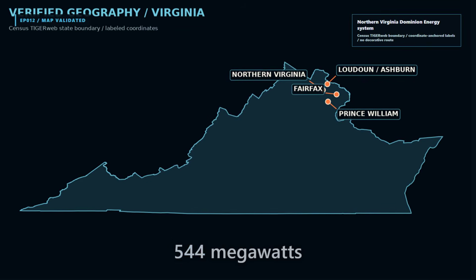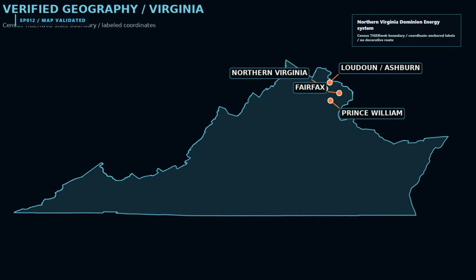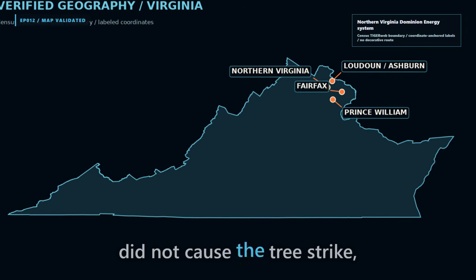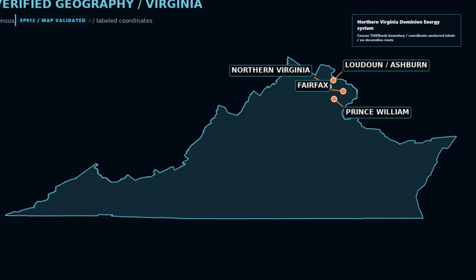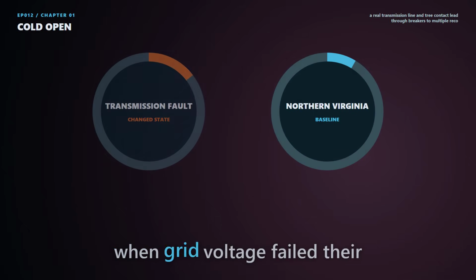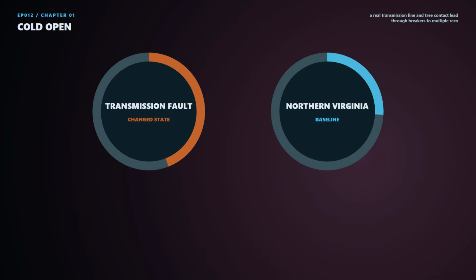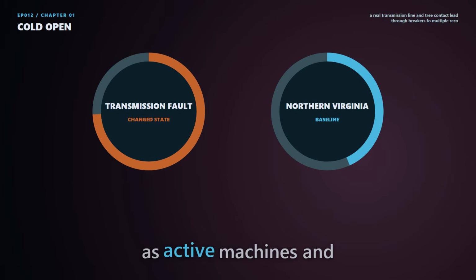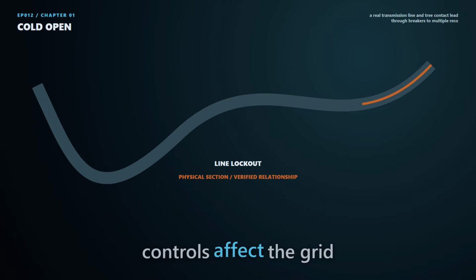Another 544 megawatts of cooperative load moved with it. The data centers did not cause the tree strike, and they did not lose power. Their controls moved them to backup when grid voltage failed their limits. Most electrical diagrams show power plants as active machines and customers as passive loads. At this scale, customer controls affect the grid too.